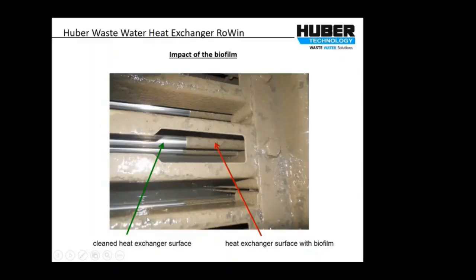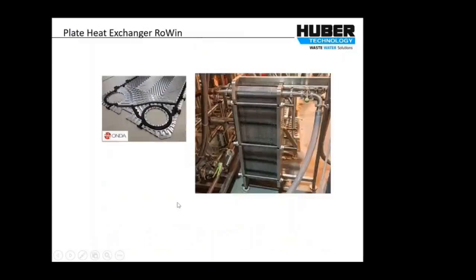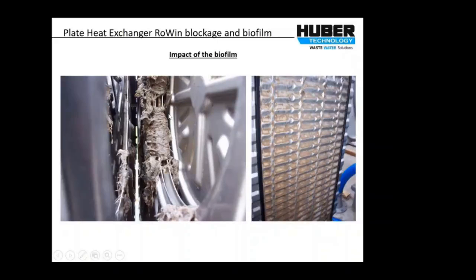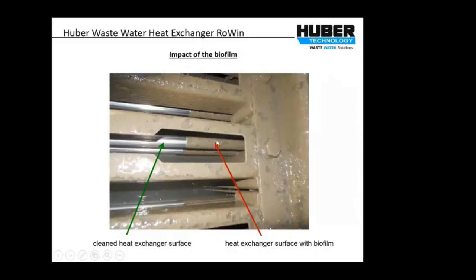A more common form of heat exchanger, which has a far higher specific surface area, so you get far more heat exchanged, is a plate heat exchanger, and these are the sorts of things that you'll find in your boiler and in other sorts of places. You can see there convoluted parts of the plate to increase the surface area, and you can see they're all squeezed together quite tightly. Well, if you put that into sewage, you really are asking for trouble. You get screenings blocking it up like this, and you get biofouling, which is much more difficult to clean, as you can imagine, than a straightforward tube where you just run a cleaning element down it and keep it clean.